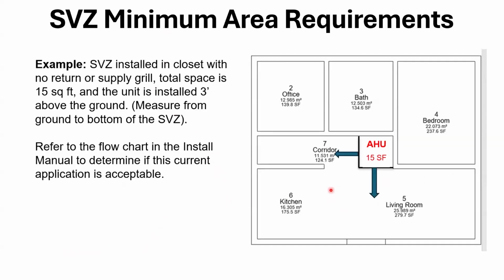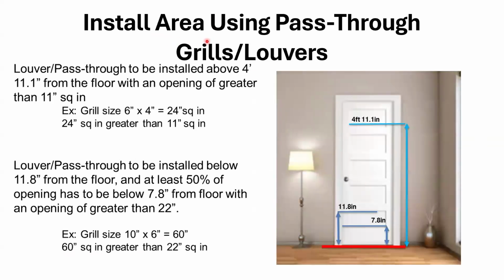So that's what we just talked about. Since we did that, we're allowed to use these in our calculation. And how we can do that is right here, installing the pass-through grills. There's a couple ways to do it. Cutting a grill into a solid wood door is not going to be fun, that'd be a mess. What I would do is undercut the door. They talk about if it's a 30-inch door and you cut it up 1 inch, you can make this bottom requirement right here. So let's talk about the top one first.